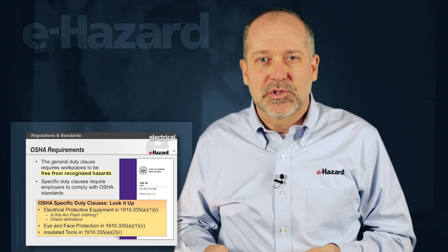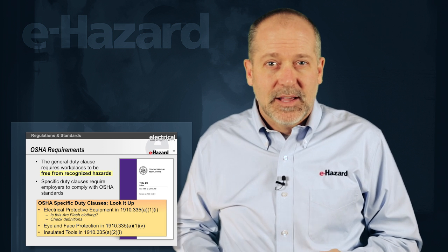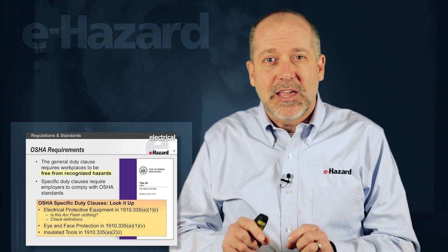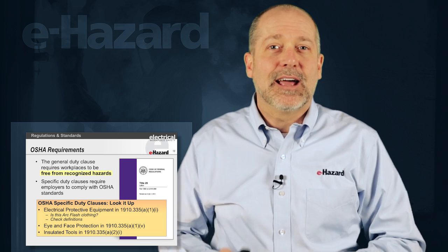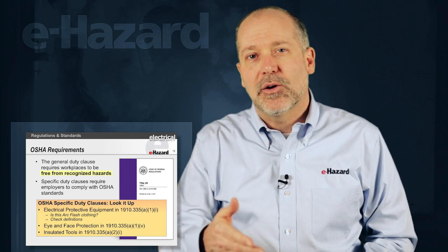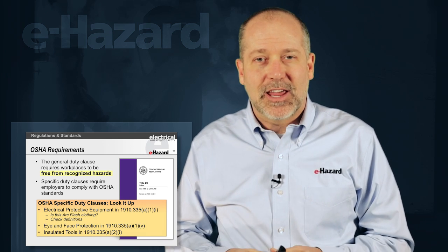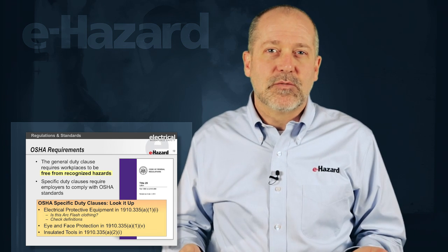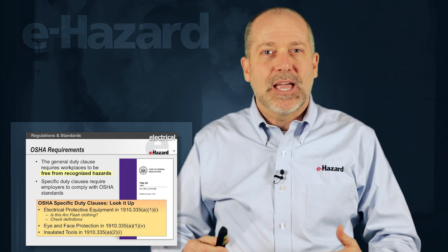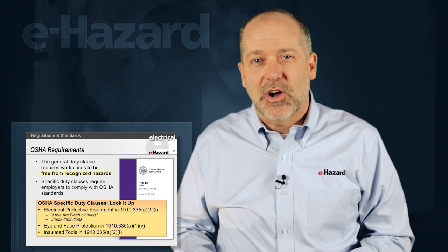Same thing with insulated tools, there wasn't actually a standard for them until after 2000. Insulated tools were required in 1991 when you worked near live parts, if you read that standard, but 'near' was not defined by OSHA. So what's the distance of near? 70E prescribes that as the limited approach boundary or the restricted approach boundary. So get into the standards, read what they're talking about, understand where those distances are, and how your tools, your rubber goods, and all those things are to be used and when they're to be used.